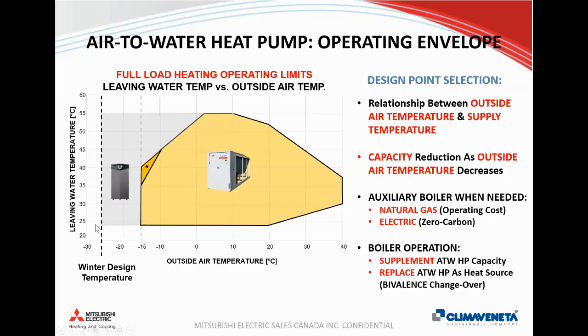So if we're looking at auxiliary boilers, because of the heat pump limitation at -15, you'll need an auxiliary boiler to run below that. So you could have a gas boiler or an electric boiler. So the electric boiler, you might want to do that if you're doing a zero carbon building. If you're trying to eliminate natural gas in that building completely, an electric boiler can still meet those design requirements. And then of course, anytime you're able to run off the heat pump instead of the electric boiler, that makes sense from a COP point of view, which we'll talk about in a couple slides.